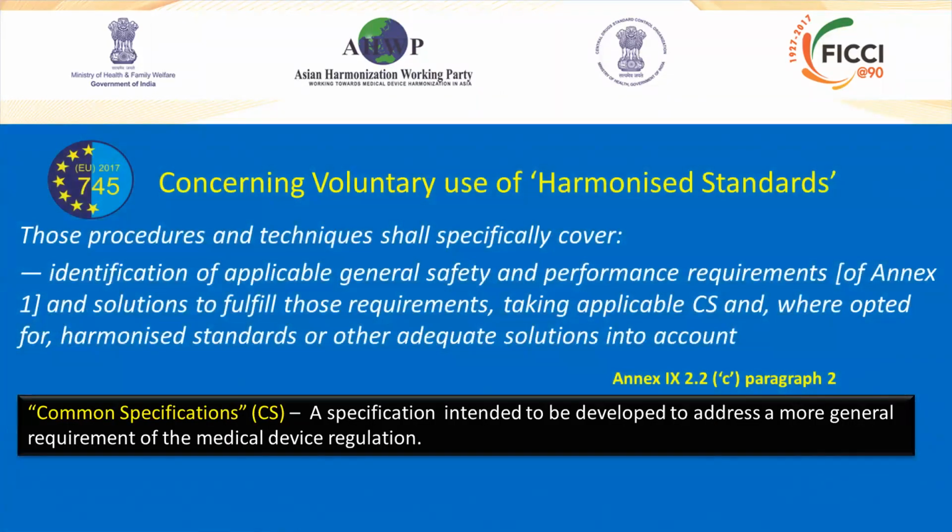There's a little bit of talk in the medical device regulation that relates to what's called harmonized standards, which are usually the ISO, IEC standards, and another thing called common specifications. And these will be something that we expect to see later developed by the regulators if there's a specification that they feel is specifically necessary for medical device safety.